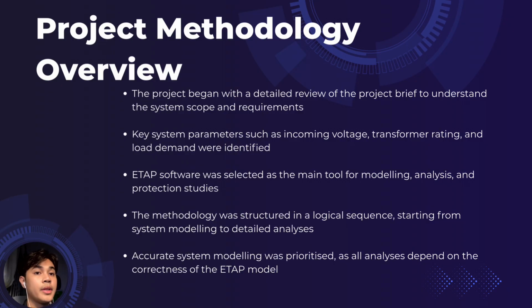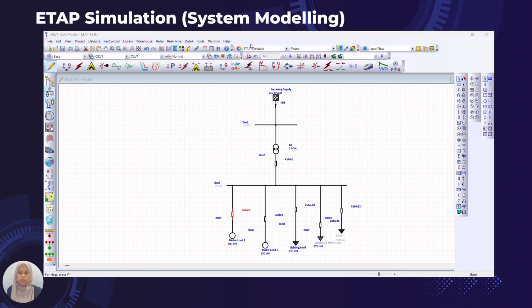As for the project methodology overview, the project began with a detailed review of the project brief to understand the scope and requirements. Key system parameters such as incoming voltage, transformer rating, and load demand were identified. ETAP software was selected as the main tool for modeling, analysis, and protection studies. The methodology was structured in a logical sequence, starting from system modeling to detailed analysis. Accurate system modeling was prioritized as all analyses depend on the correctness of the ETAP model.